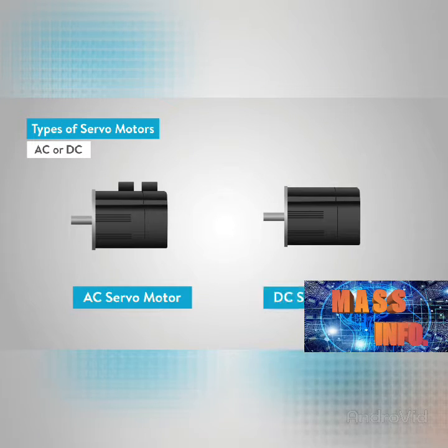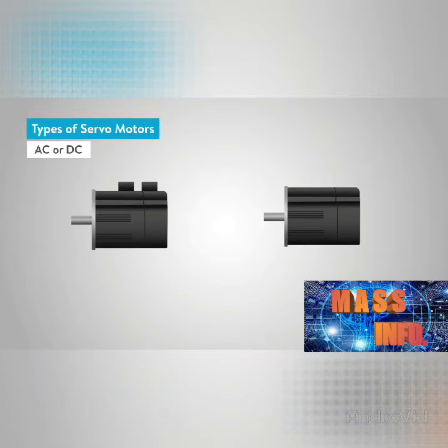AC or DC consideration is the most basic classification of a motor based on the type of current it will use. Looking at it from a performance standpoint, the primary difference between AC and DC motors is in the inherent ability to control speed. With a DC motor, the speed is directly proportional to the supply voltage with a constant load.